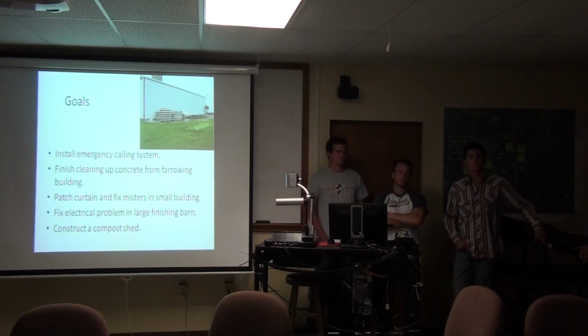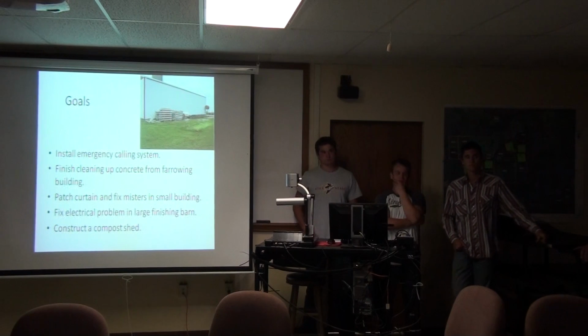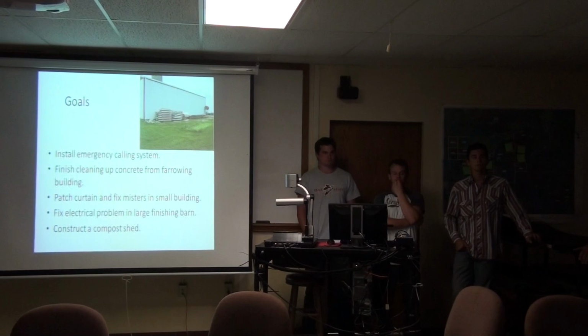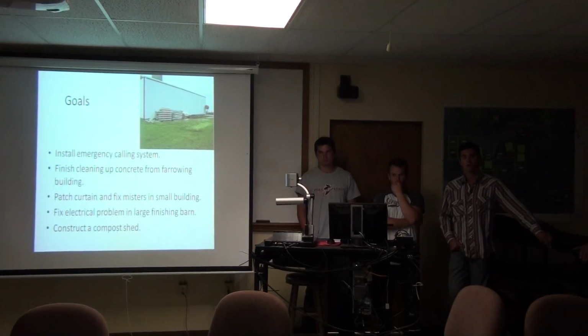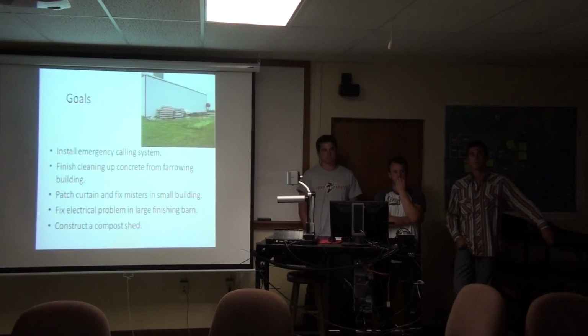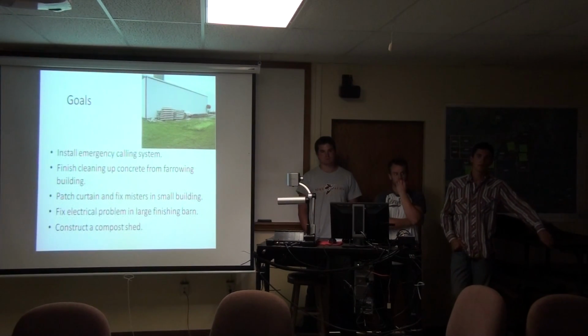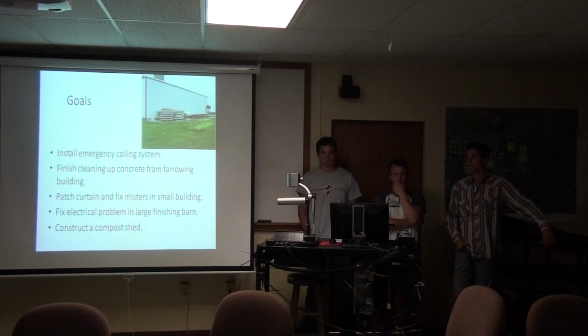The fans are just a replacement motor, so we can handle that, but this electrical problem has me baffled, because it's just on the east side of the building. The other thing is, none of the misters work on automatic. In the other three rooms, they work on manual; you can shift to manual and they'll kick right in. But on automatic, the light comes on, but it doesn't activate. I don't know if we took a lightning strike or what, but something's kind of screwy, so we're working on that, and we'll get it fixed.